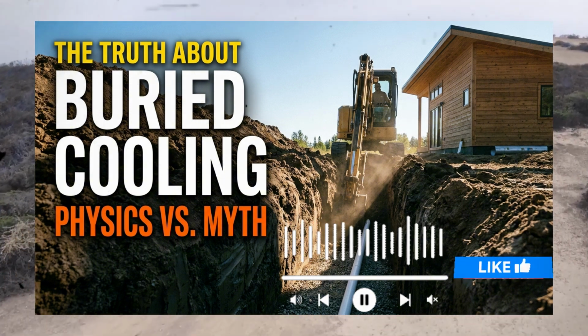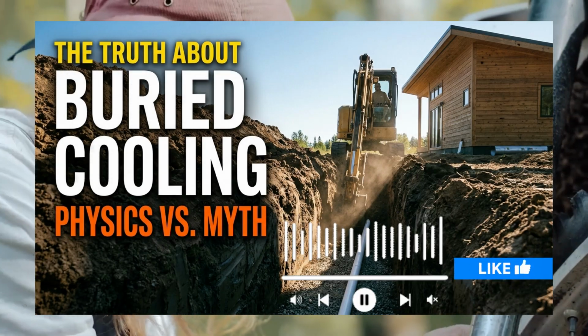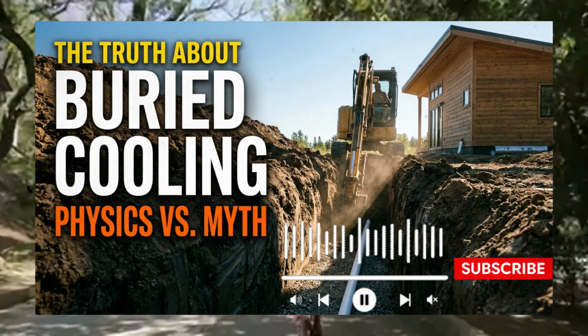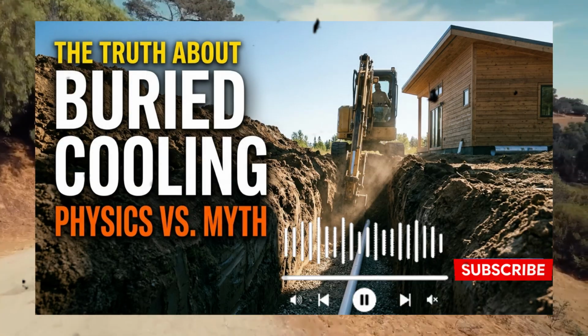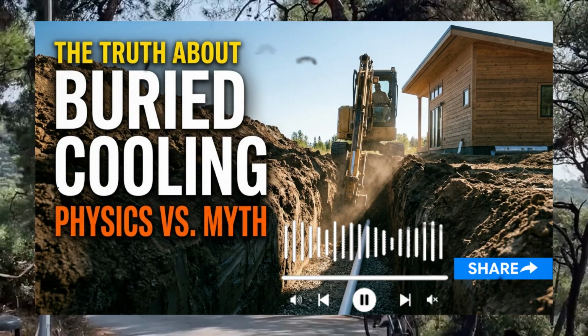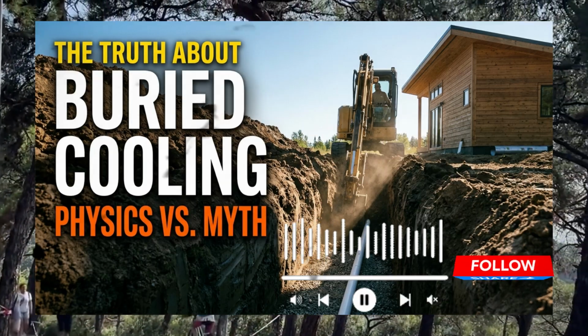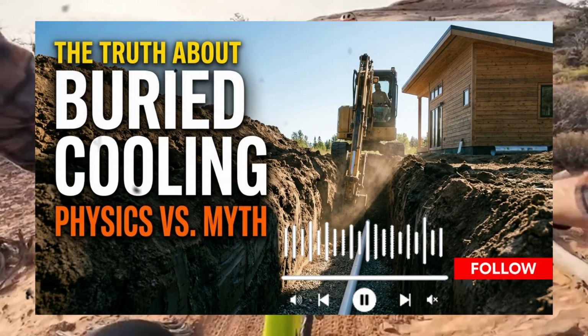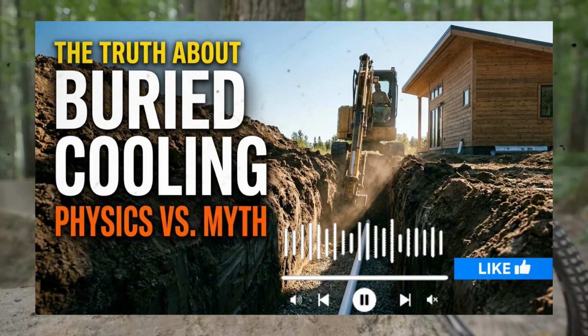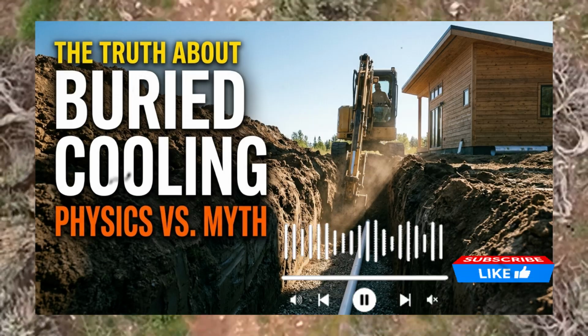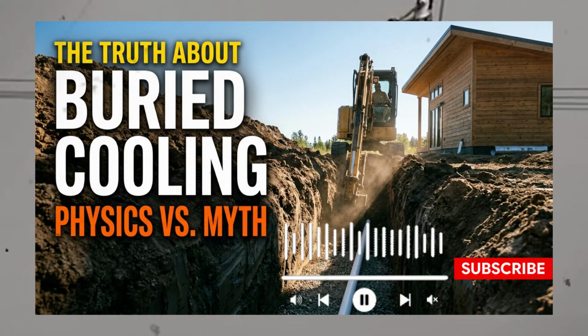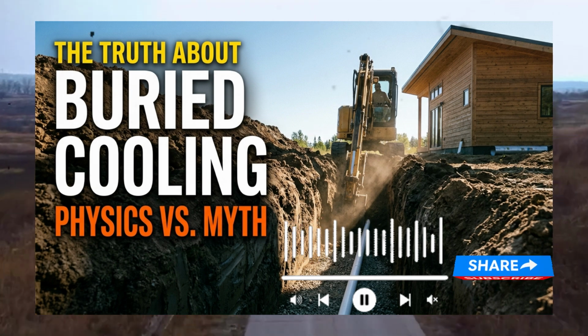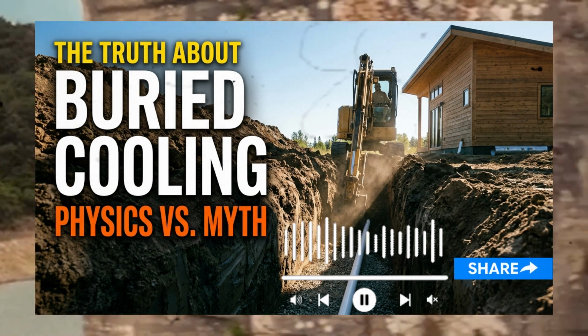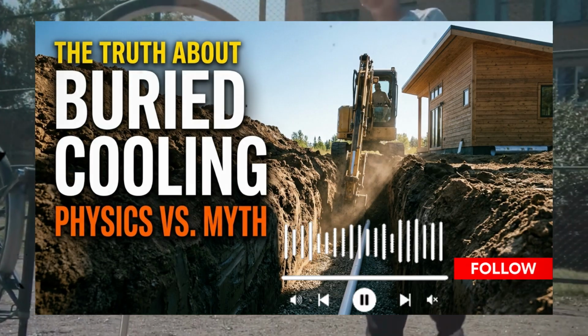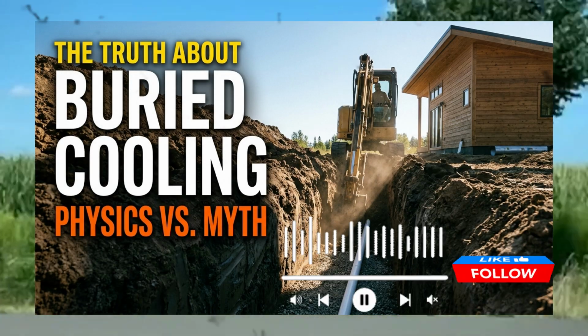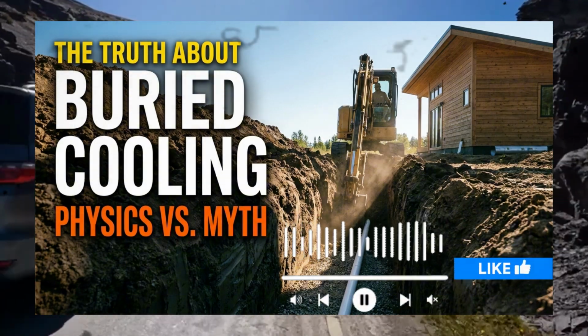To understand the energy dynamics of this thermal exchange, we have to look at the volumetric flow rate. Our inline direct current blower was moving exactly 250 cubic feet per minute of air through our 6-inch pipe network, using the standard formula for sensible heat transfer, where the cooling capacity in British thermal units per hour is calculated by multiplying the volumetric flow rate by the temperature difference and a constant of 1.08. We find that our system was producing 8,640 British thermal units per hour of continuous, sensible cooling. Think about that for a second. That is nearly 3/4 of a ton of air conditioning capacity.